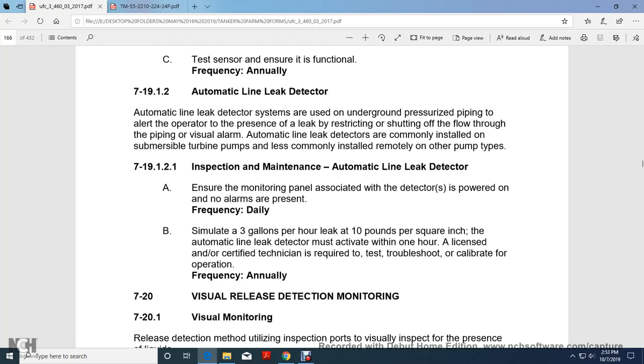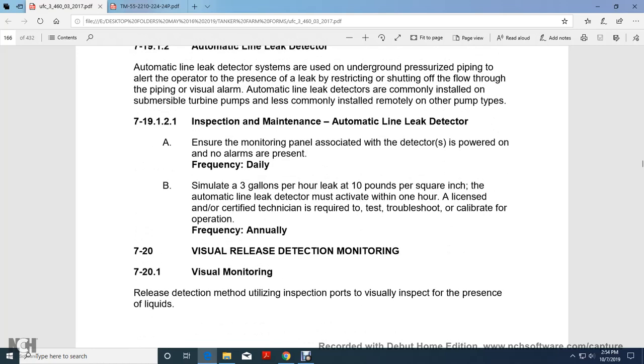719.12 Automatic line leak detector. Automatic line leak detector systems monitor underground pressurized piping to alert the operator to the presence of a leak by restricting or shutting off the flow of fluid from the piping, or by visual alarm. Automatic line leak detectors are commonly installed with submersible turbines, and less commonly installed with the other pump types. 719.121 inspection maintenance automatic line leak detector.